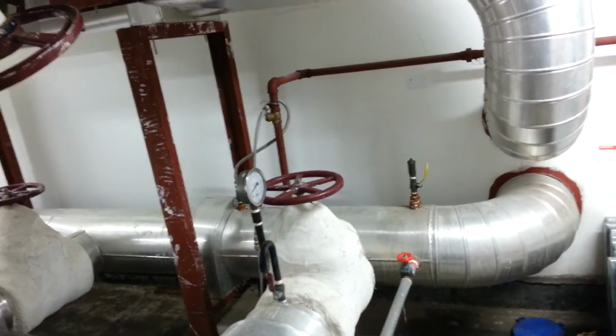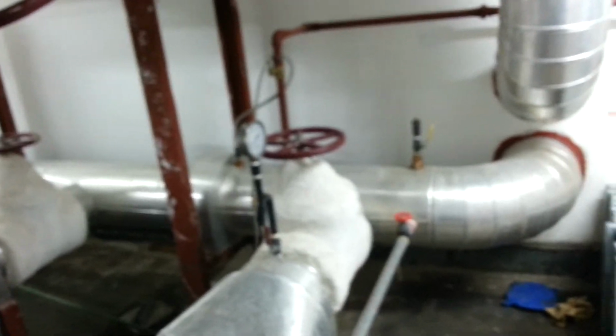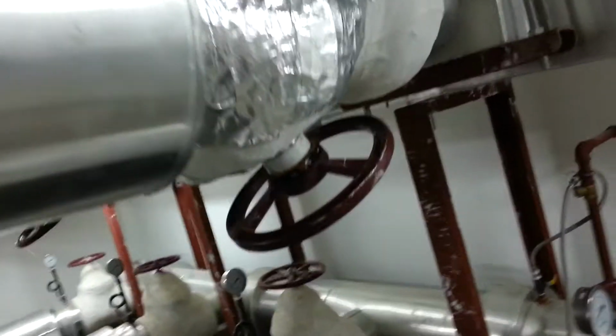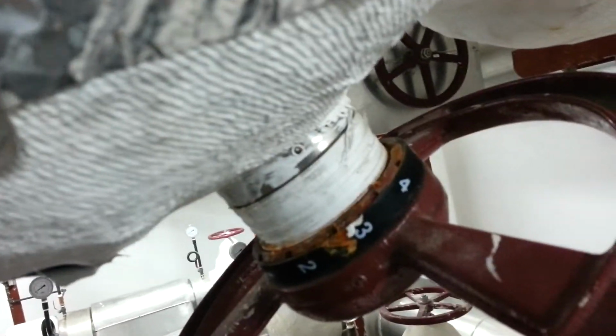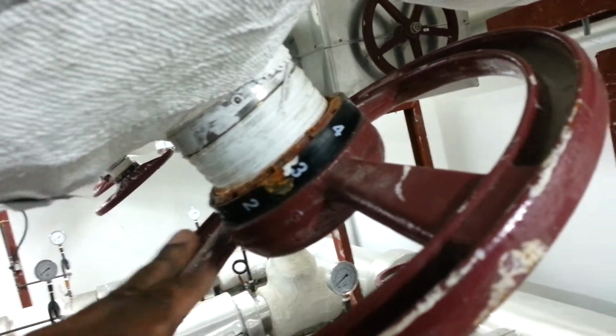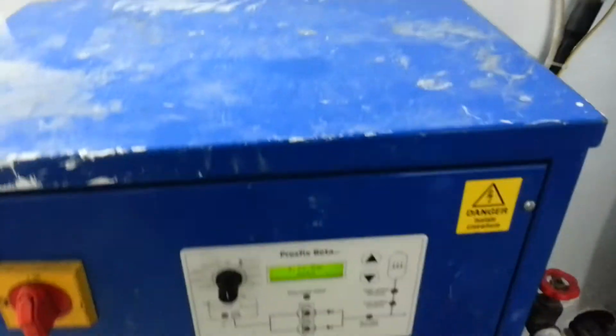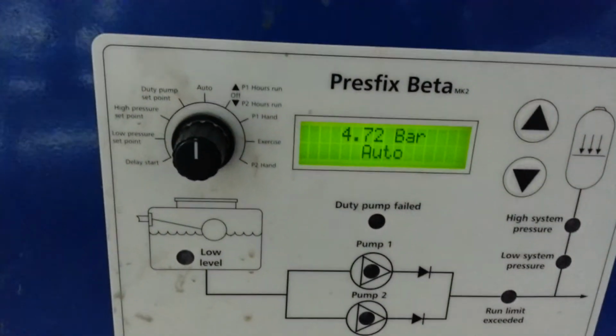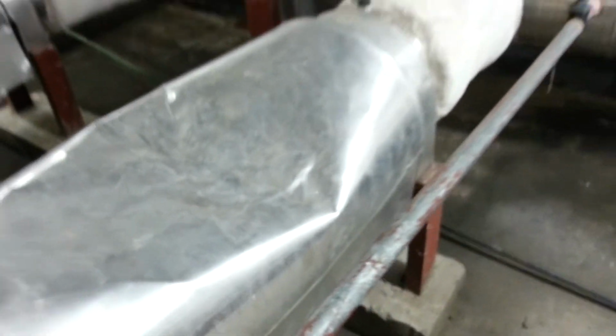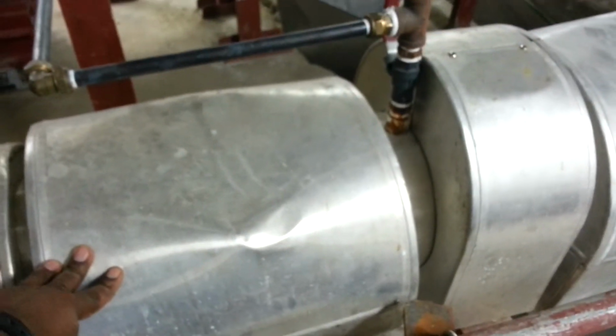This is the discharge, and here you can see there is a gate valve, and here there is a balancing valve. With the specialty balancing valve, we can adjust the exact percentage of flow. And here is the air vent for removing the air from the chill water line. And this is the makeup tank. Here we can adjust the pressure. And this is the strainer. This is the strainer for the chill water pump, and here you can see this NRV, non-return valve.